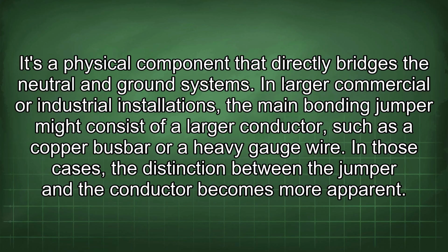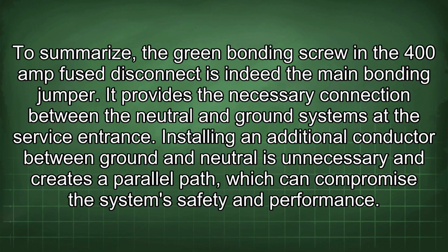In larger commercial or industrial installations, the main bonding jumper might consist of a larger conductor, such as a copper busbar or a heavy gauge wire. In those cases, the distinction between the jumper and the conductor becomes more apparent. To summarize, the green bonding screw in the 400 amp fused disconnect is indeed the main bonding jumper. It provides the necessary connection between the neutral and ground systems at the service entrance.